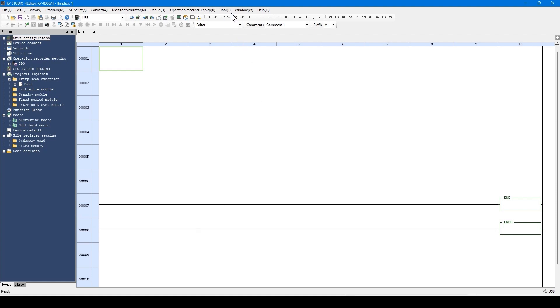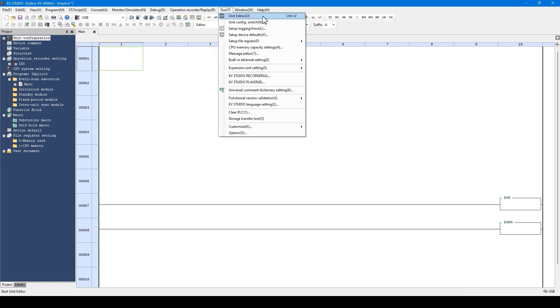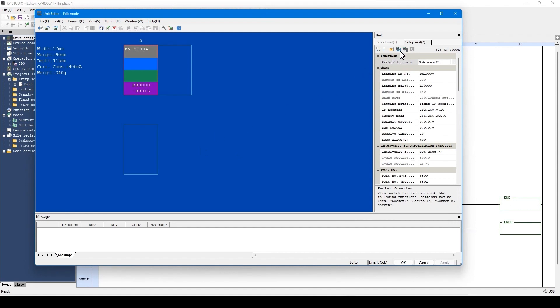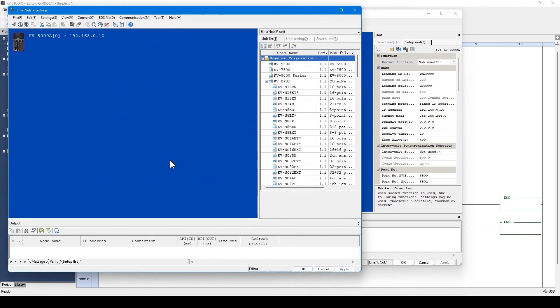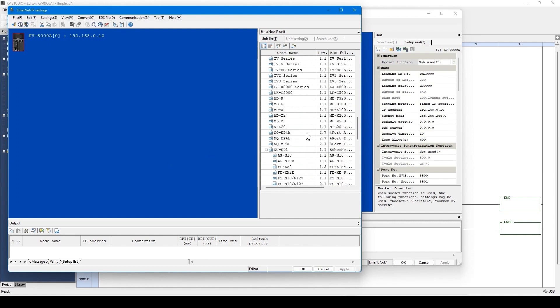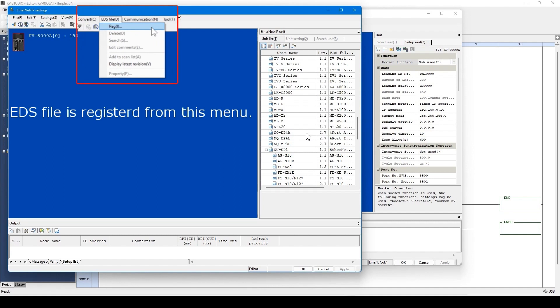First, open the unit editor. Then open the Ethernet IP settings window using this icon. Since the unit is not made by Keyence, it will not be displayed in this list. Therefore, an EDS file from the device manufacturer is needed. This contains the necessary information to set up communication. I'll need the EDS file from the FANUC website and register it to KV Studio.